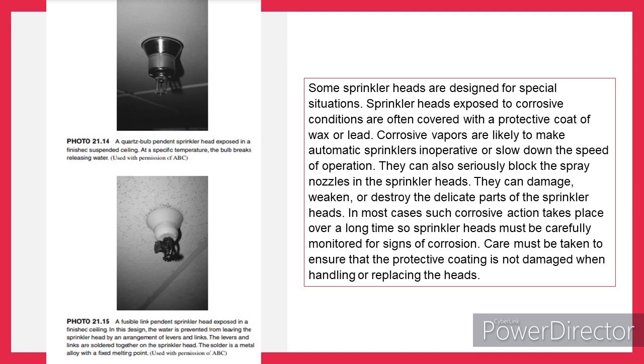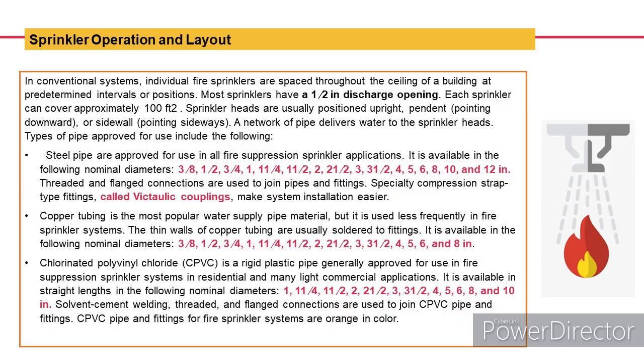Sprinkler heads exposed to corrosive conditions are often covered with a protective coat of wax or lead. Corrosive vapors are likely to make automatic sprinklers inoperative or slow down the speed of operation. They can also seriously block the spray nozzles in the sprinkler heads. They can damage, weaken, or destroy the delicate parts of the sprinkler heads. In most cases such corrosive action takes place over a long time, so sprinkler heads must be carefully monitored for signs of corrosion. Care must be taken to ensure that the protective coating is not damaged when handling or replacing the heads. Operation and layout must also be considered in installing sprinklers.